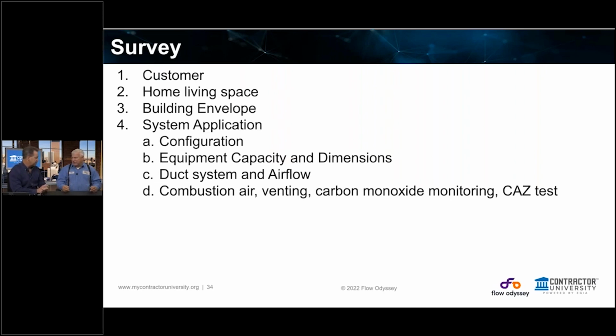There's very few 40%ers. You look outside, and I pictured 7 of them from my hotel room. Yeah, that'd be a 50, 60-year-old furnace. Well, they're out there. Maybe. Okay. So if you look at the flue and it's all nasty on the outside. Yeah. If you look on top of the roof, the flue is rusty and it's just nasty. And then yesterday I saw ice buildup on 4 of the 7 atmospheric flues from my hotel room.